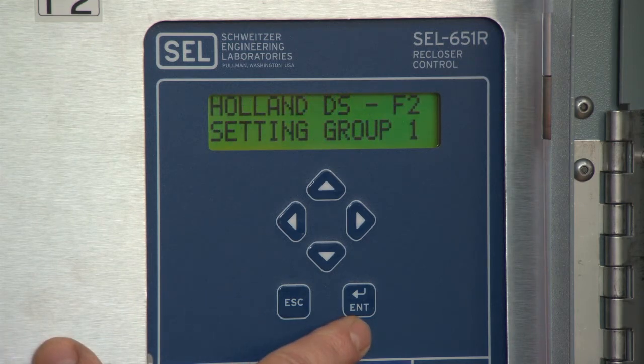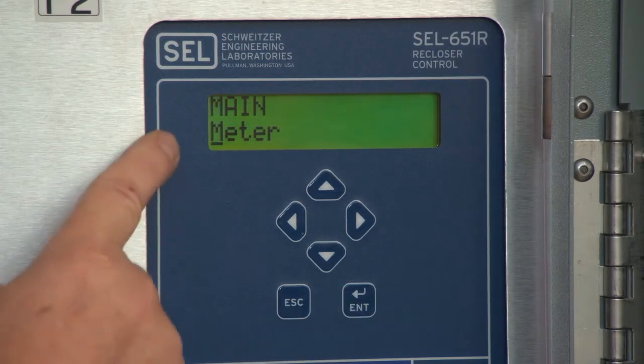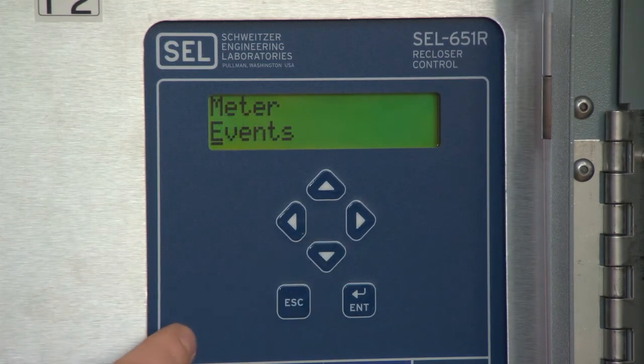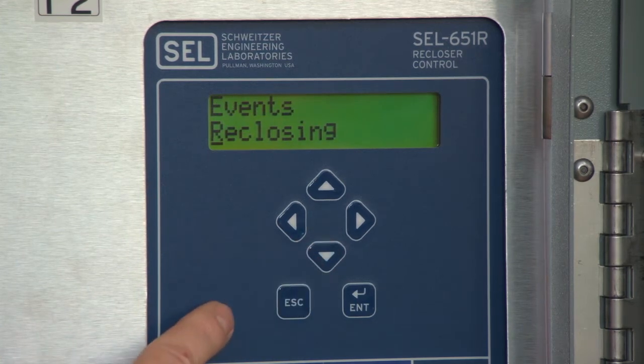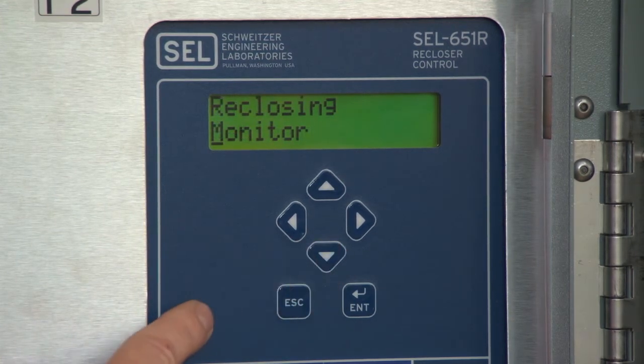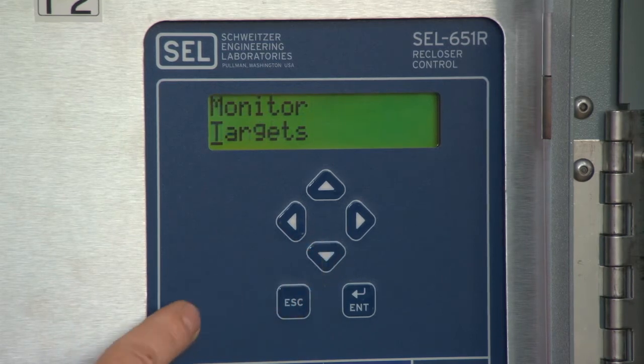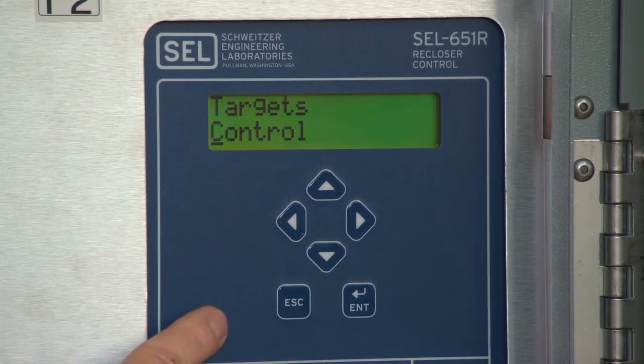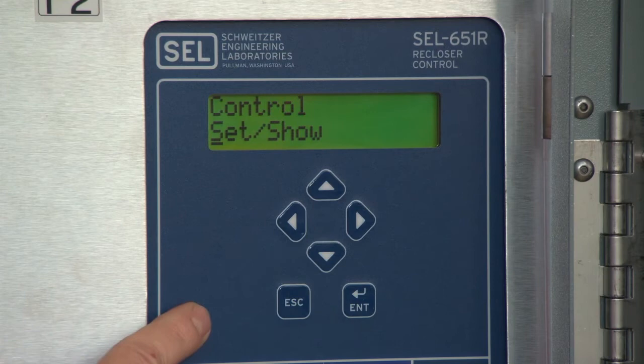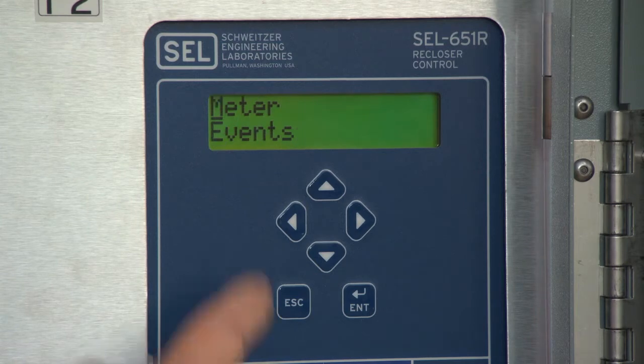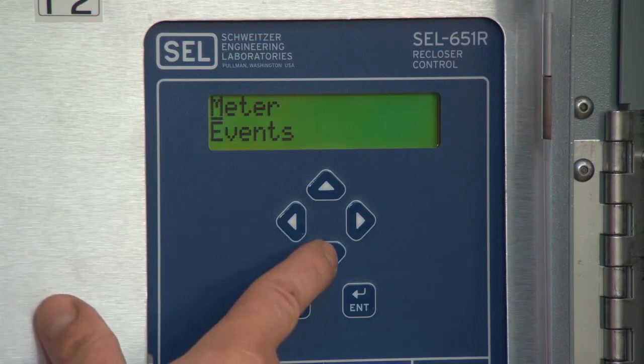Pressing the enter button will allow you to scroll through a series of screens such as meter, events, reclosing, monitor, targets, control, and settings, which allows you to change the functionality of the recloser. The only screen that a lineman will really be interested in is the events. Let's take a closer look at events.